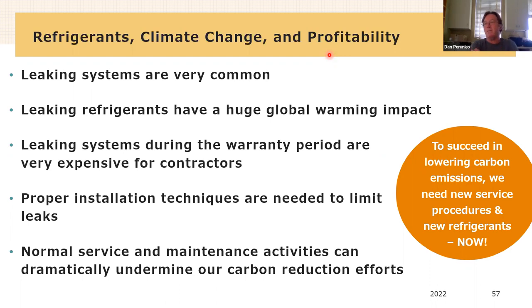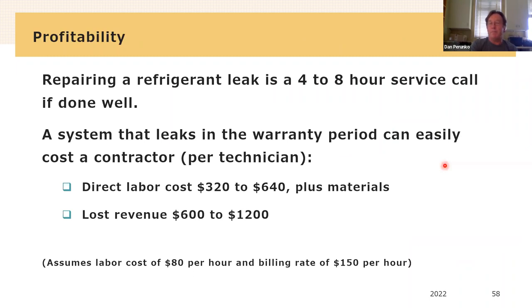And then as a contractor, if you're moving into refrigerant systems, air conditioners and heat pumps, pardon me, leaks that occur in the warranty period where you can't bill the customer for it are expensive. You're looking at six hours of time typically to fix the system. And you end up having to pay all that out of pocket. So leaks are very expensive for contractors initially. Later, service contractors can make a lot of money on them. So anyway, time to change procedures and do a better job about all of this.